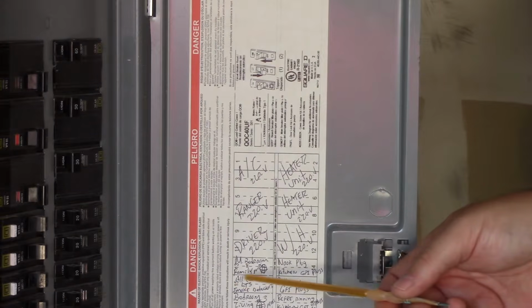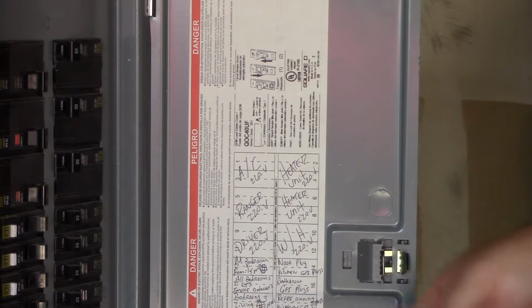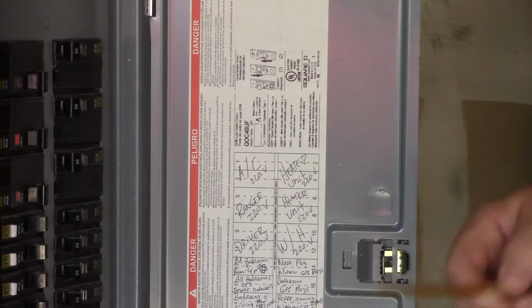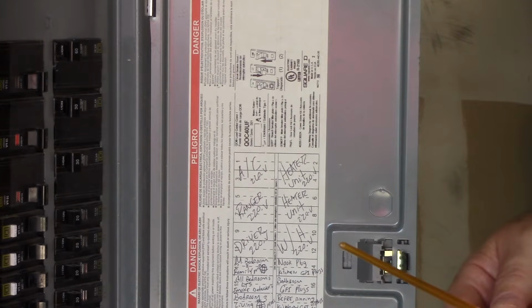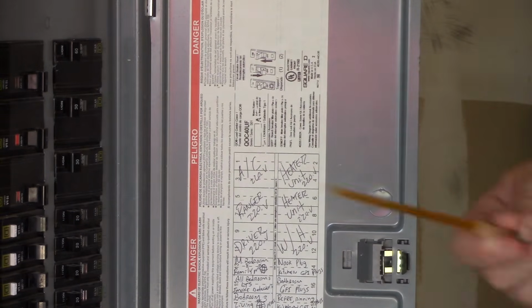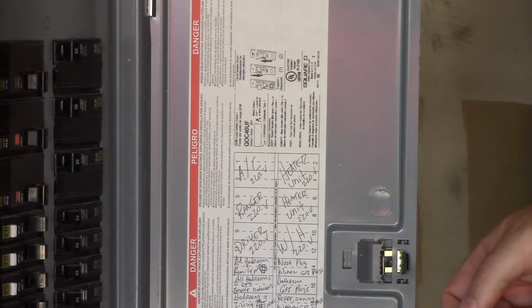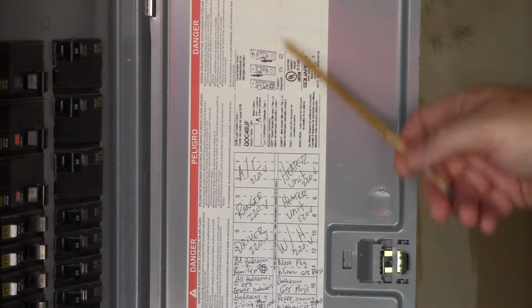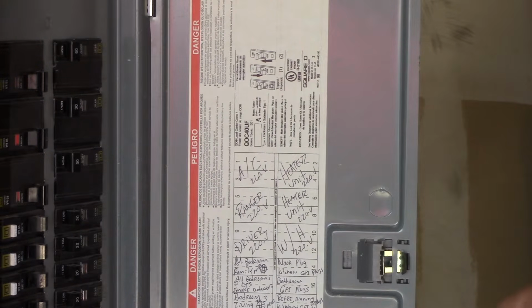But the other ones say all bedrooms, lighting, bedrooms, receptacles. They need to be more descriptive on which bedroom we're talking about. If it says Susie's bedroom here, then we have a problem because Susie might not live here anymore. Obviously, if it's getting a home inspection, Susie's probably gone. If we're getting a municipal inspection, and this is the final part of it, nobody's even moved in yet, so how could they know it was Susie? So it needs to be more descriptive than that. It needs to be very clear, and 408 gives us that direction, with requirements to have the directory very distinctively clear on what it serves.